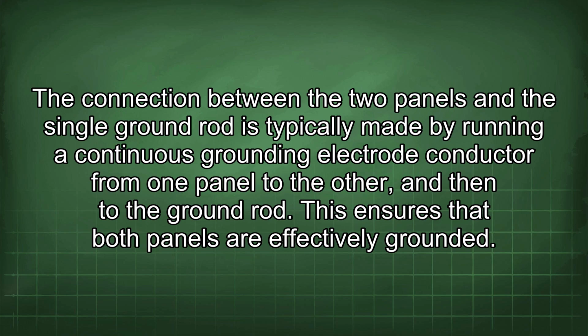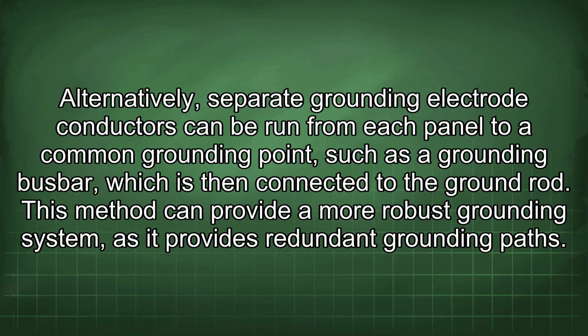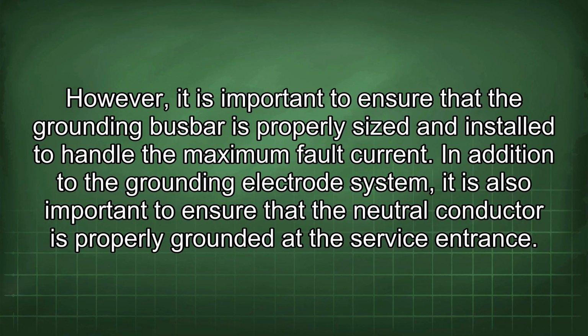This ensures that both panels are effectively grounded. Alternatively, separate grounding electrode conductors can be run from each panel to a common grounding point, such as a grounding busbar, which is then connected to the ground rod. This method can provide a more robust grounding system, as it provides redundant grounding paths.